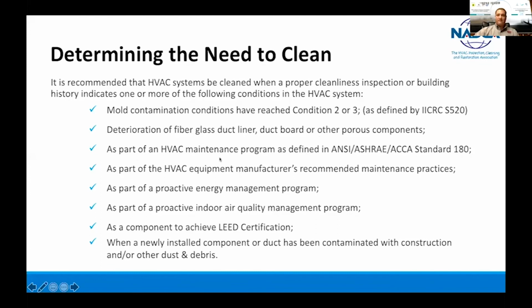HVAC maintenance program as defined by ANSI ASHRAE standard 180, as part of the HVAC equipment manufacturer's recommended maintenance practices, as part of a proactive energy management program, as part of a proactive indoor air quality management program, as a component to achieve LEED certification, or when a newly installed component or duct has been contaminated with construction and or other dust and debris. And as you can see through here, all I did was basically give you more things to go read up on for determining the need to clean based off certain parameters that you would find within these other standards.